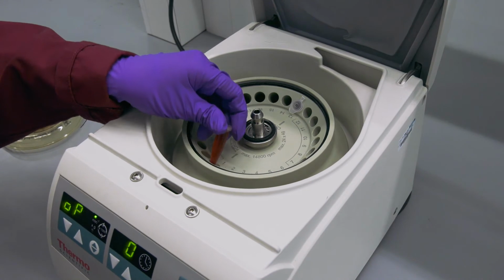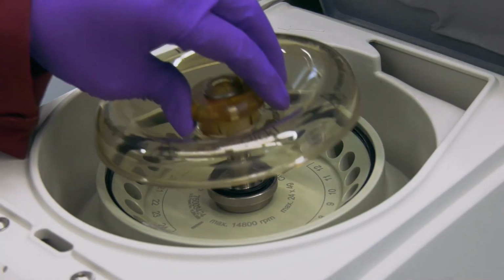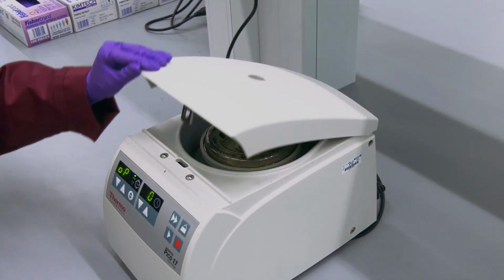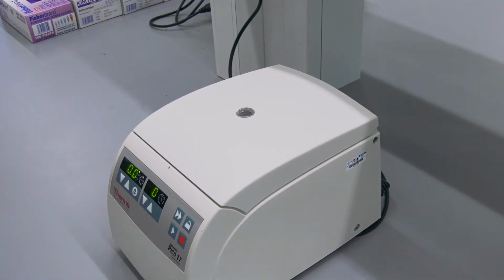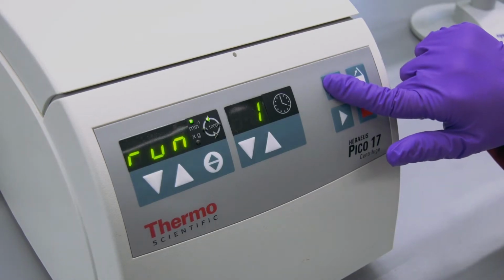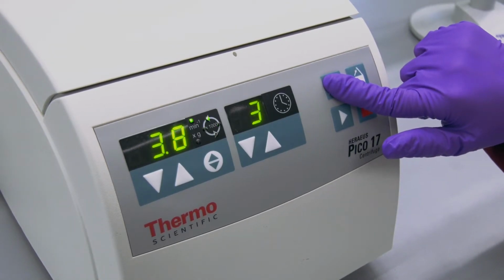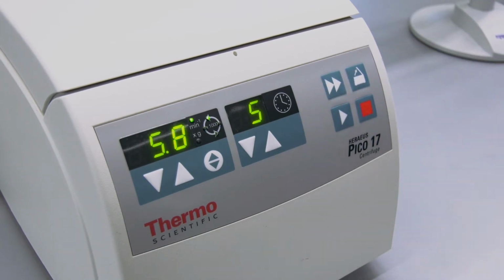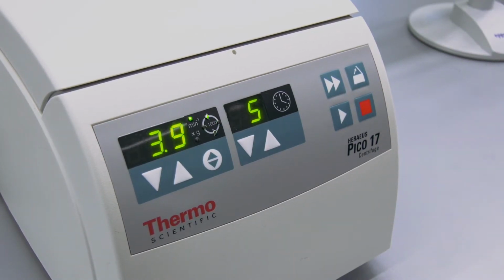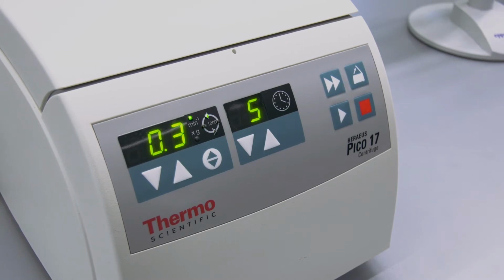Brief centrifuge. Sometimes you'll be asked to briefly centrifuge a sample. To do this, simply load your sample without setting a time and speed. Put the protective cover on the rotor and shut the lid as normal. Rather than running a program, simply press and hold the pulse button for 4 to 5 seconds. This is all that is required to briefly centrifuge a sample.